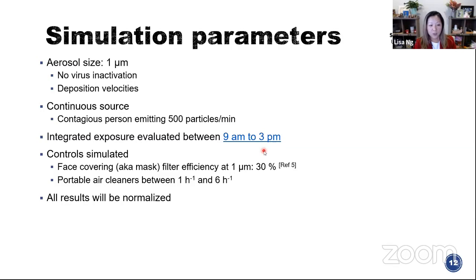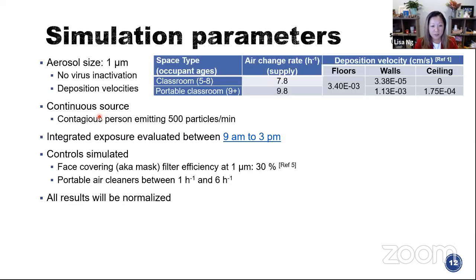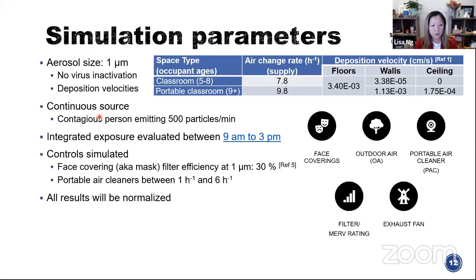We looked at an aerosol size of one micron. We did not look at virus inactivation, mostly because data is not yet out on how UVGI may affect this virus. We did look at deposition velocity and assumed a contagious person emitting 500 particles per minute as the constant source in FATIMA. We assumed an integrated exposure between 9 AM and 3 PM — a typical time children would be in school. Controls studied included face coverings for both the person being exposed and the contagious person.